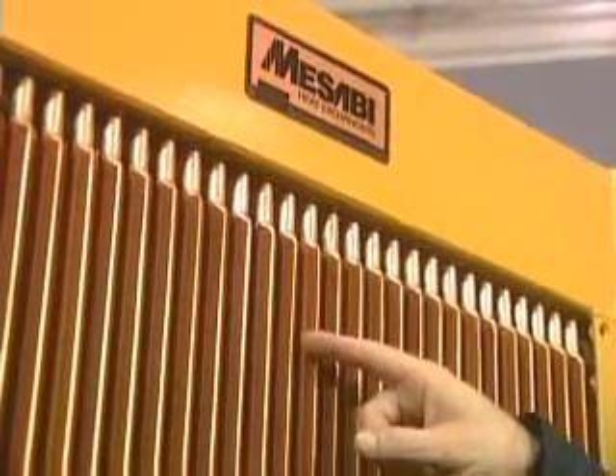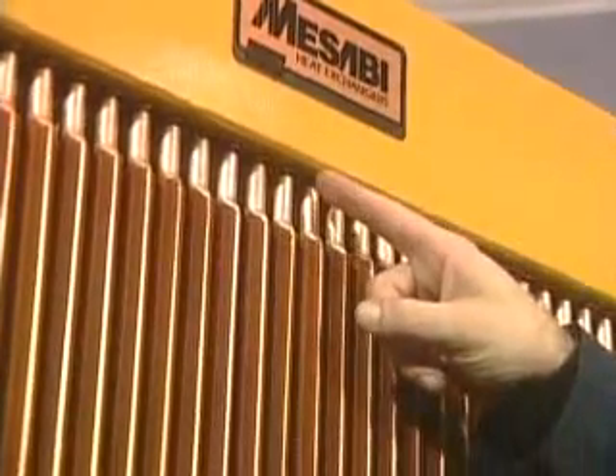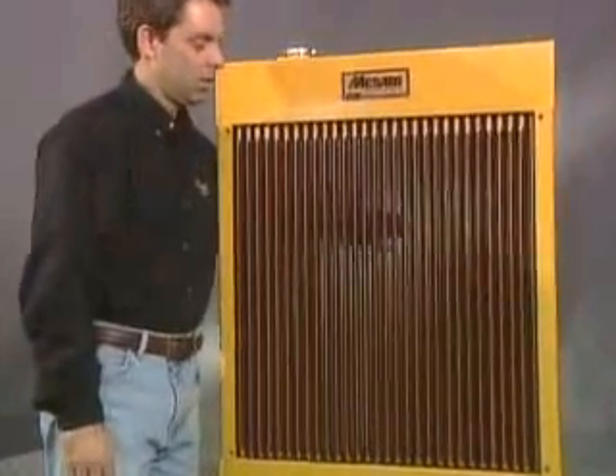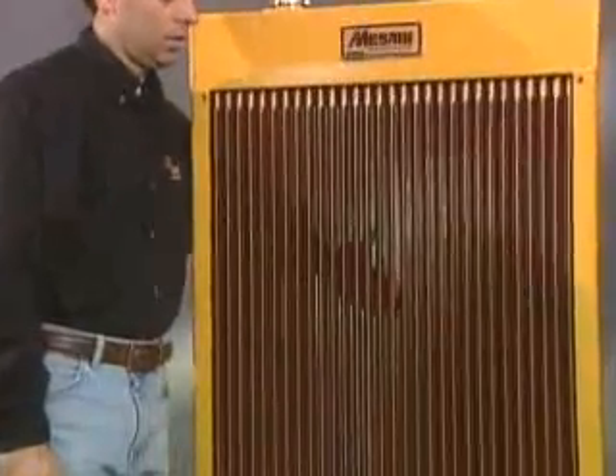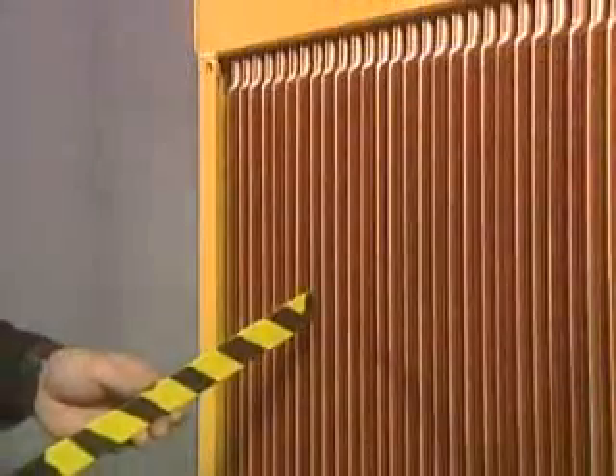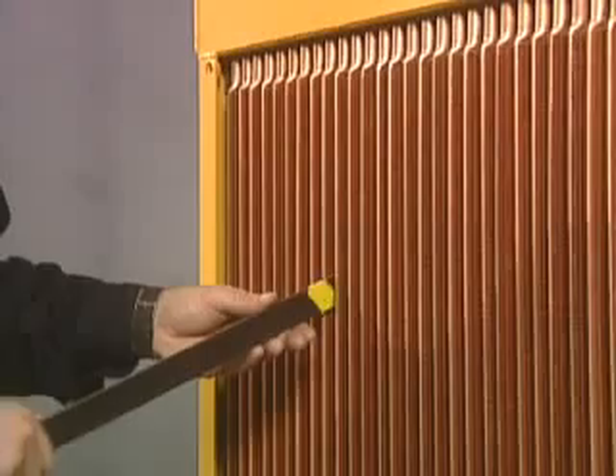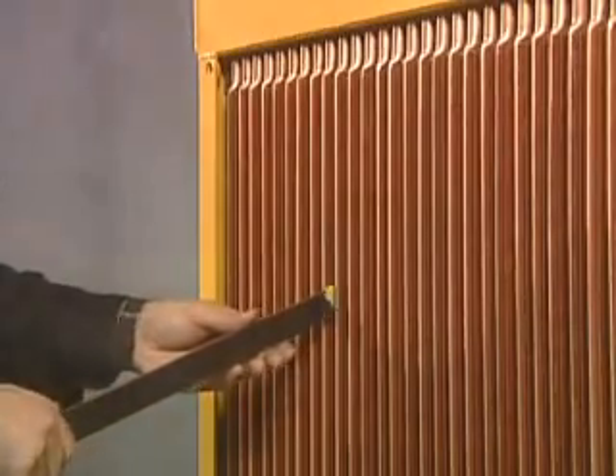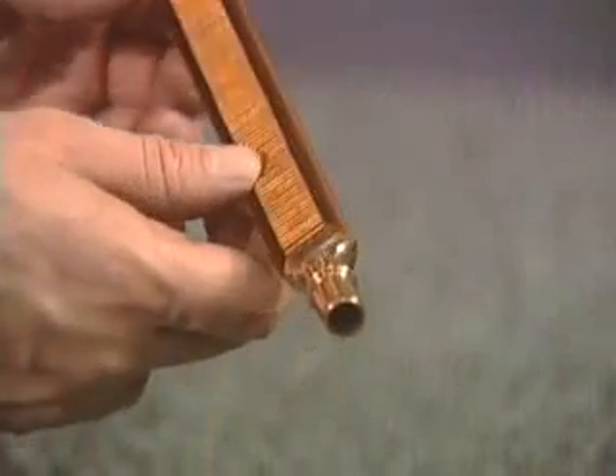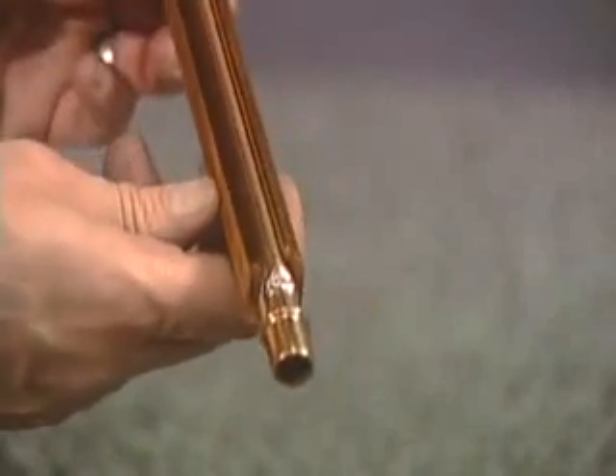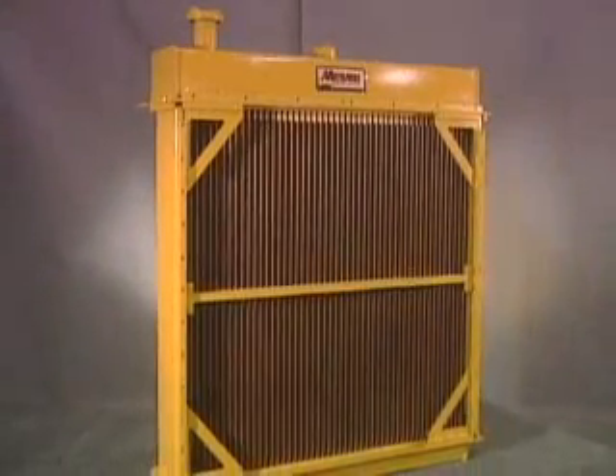Debris too large for passages can be easily blown off with high-pressure water or air. And you don't have to worry about the fins folding over like you do with conventional cores. The leading edge of the tube finning is V-shaped to let debris slide past without getting caught on fin edges. For the construction industry, L&M has developed retrofits for the Caterpillar folded and modular core radiators.